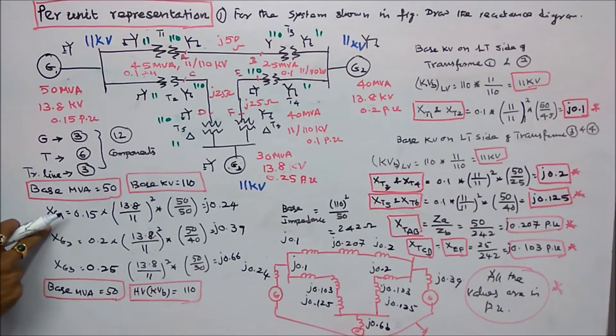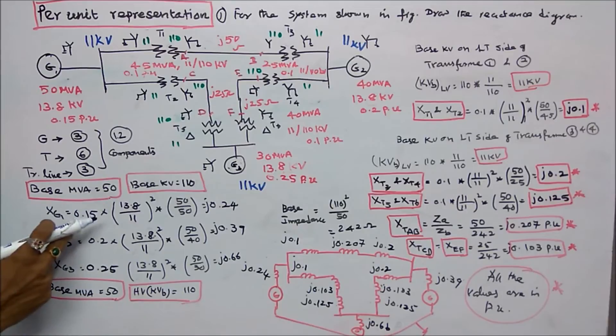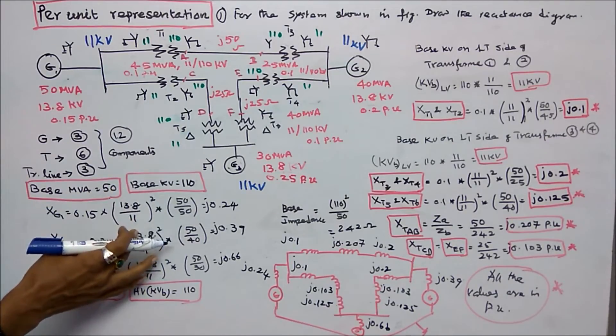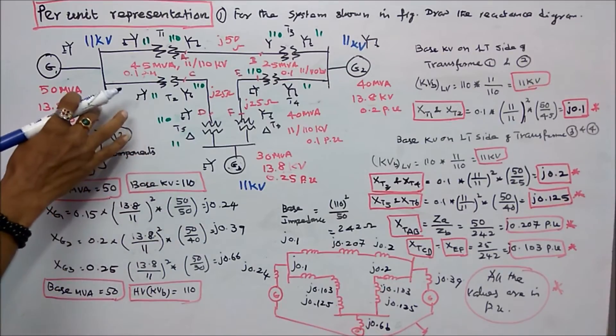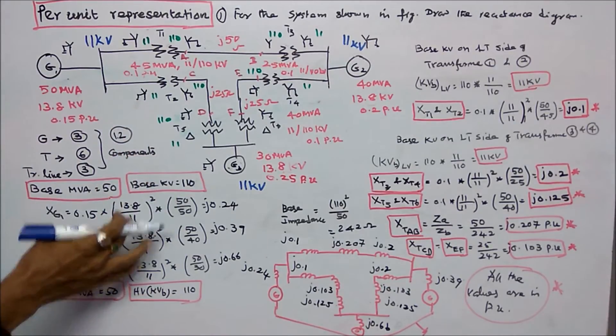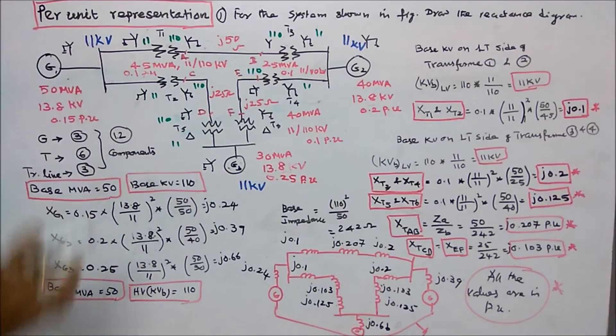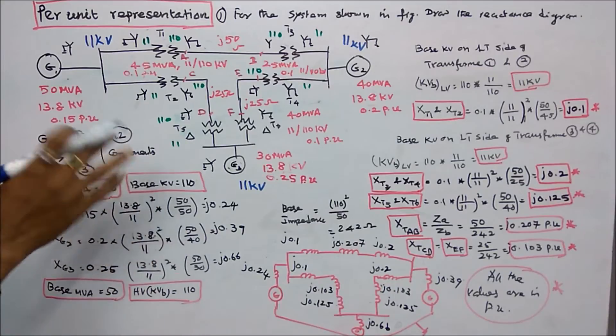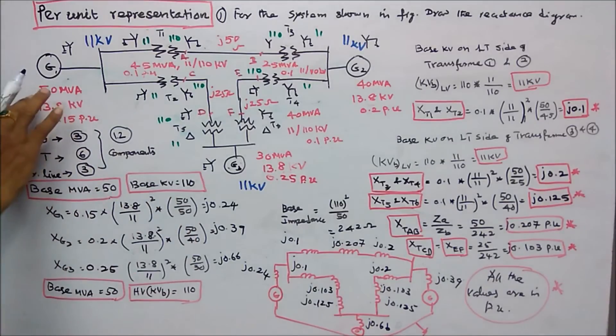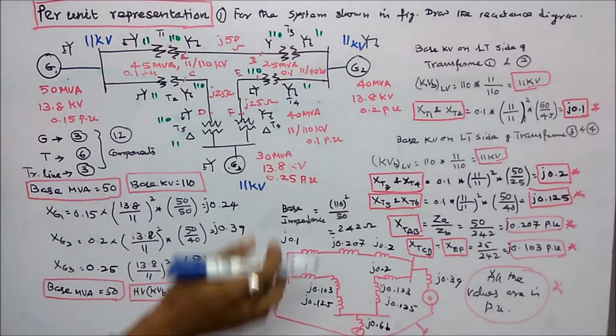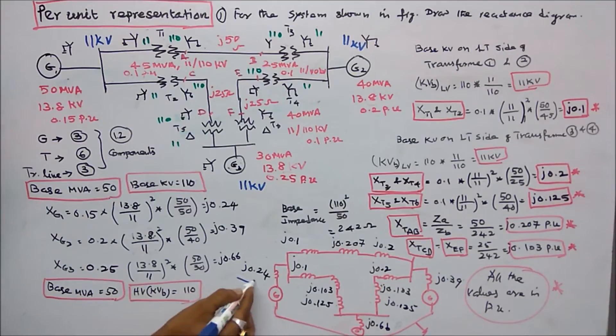Generator 1 per unit reactance = 0.15 × (13.8/11)² × (50/50) = j0.24. This is the new per unit reactance for generator 1.